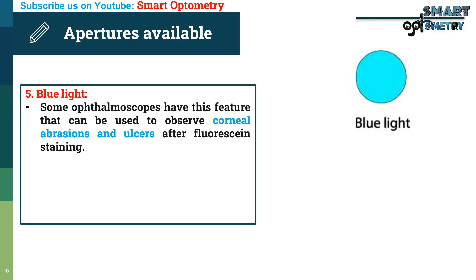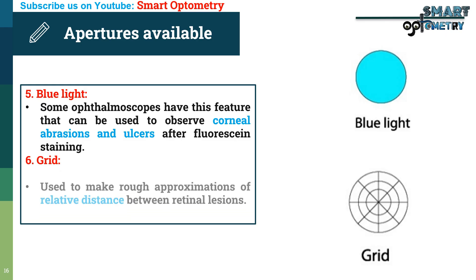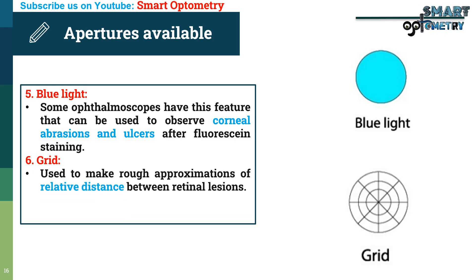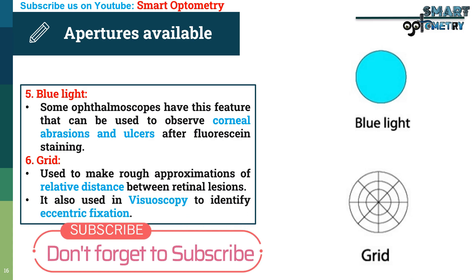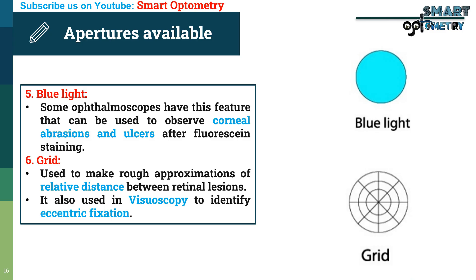5. Blue light: some ophthalmoscopes have this feature, which can be used to observe corneal abrasions and ulcers after fluorescein staining. 6. Grid: used to make a rough approximation of relative distances between retinal lesions. It is also used in visuoscopy to identify the amount of eccentric fixation.